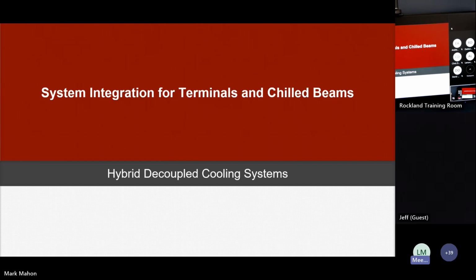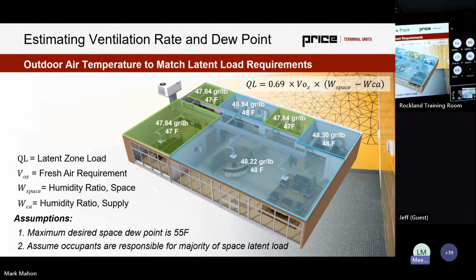Yeah. Did you check your sensible? Some situations I've seen using that analysis, yeah, you absolutely could, in some cases, require some reheat on internal zones depending on the market. It's certainly possible. I would say generally when we look at a design day summer condition, which is kind of what I'm assuming and looking at here, we're going to need enough cooling in those internal zones too, that we usually aren't overcooling the space requiring reheat. But analysis would be good to look at depending on the project, and a risk of overcooling is a consideration with DOAS systems at times if you're taking this kind of approach.